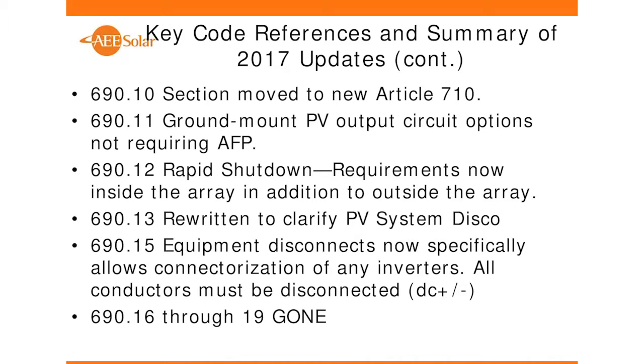690.11 is our arc fault section. Arc fault section of the code, as I said, went from buildings only to ground mount as well, and then in the 2017 code we put some exceptions in for ground mount systems. And those exceptions are that you do not have to have arc fault protection on PV output circuits that are either buried or in metallic raceways. So the output circuit is not required to have arc fault detection on it, but the source circuits still are required to have arc fault detection on a ground-mounted system.